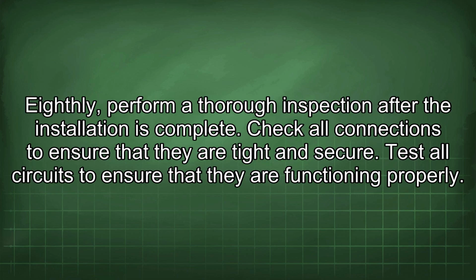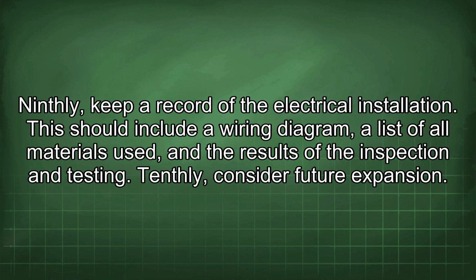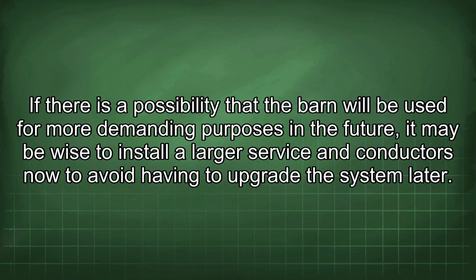Eighthly, perform a thorough inspection after the installation is complete. Check all connections to ensure that they are tight and secure. Test all circuits to ensure that they are functioning properly. Ninthly, keep a record of the electrical installation. This should include a wiring diagram, a list of all materials used, and the results of the inspection and testing. Tenthly, consider future expansion. If there is a possibility that the barn will be used for more demanding purposes in the future, it may be wise to install a larger service and conductors now to avoid having to upgrade the system later.